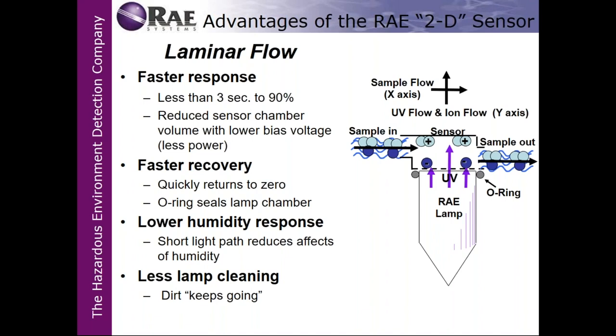The thing that makes our system a little bit simpler is that it quickly gets to zero. And if you change a PID in our monitor, there's an O-ring seal on the lamp chamber. So it allows the gas to flow through the chamber and not flow freely within the meter itself, causing a false positive.